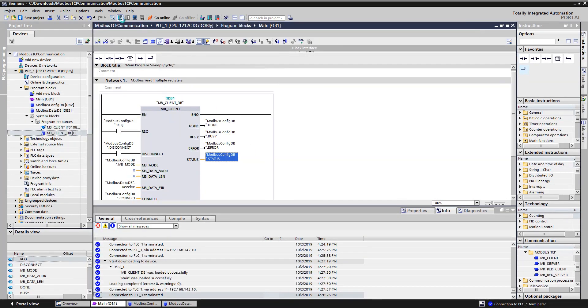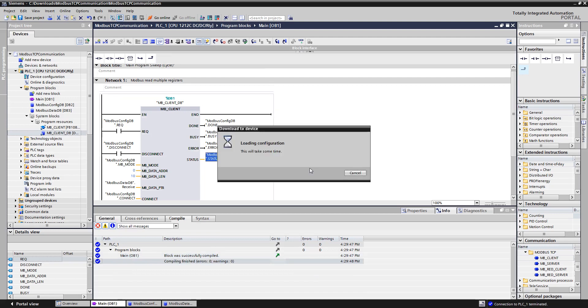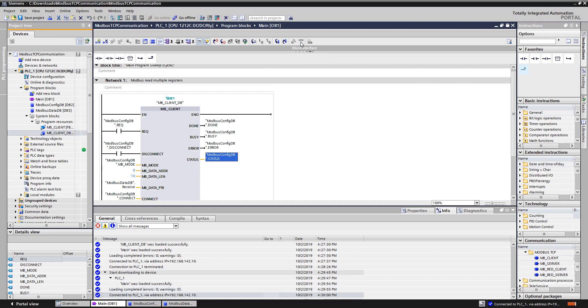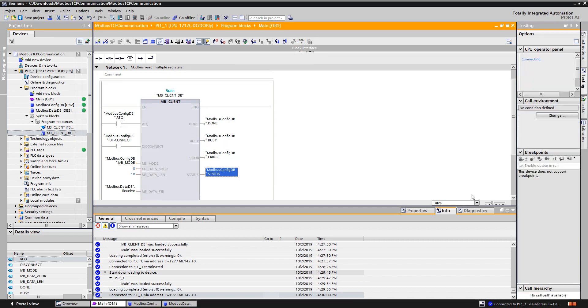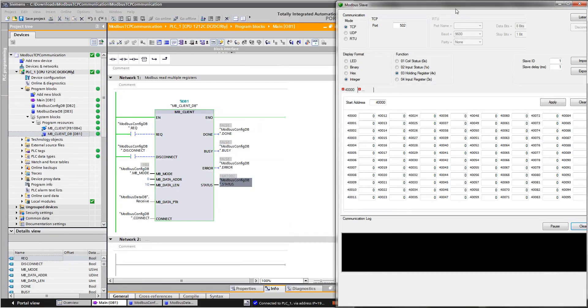Data PTR is the receiving array in the DB. That should be all — now just download the program. I'm using Modbus Slave software which is running on the PC, connected to the PLC by Ethernet cable and has the IP defined in the connection DB. In the client, select the right port, write address, and click listen.